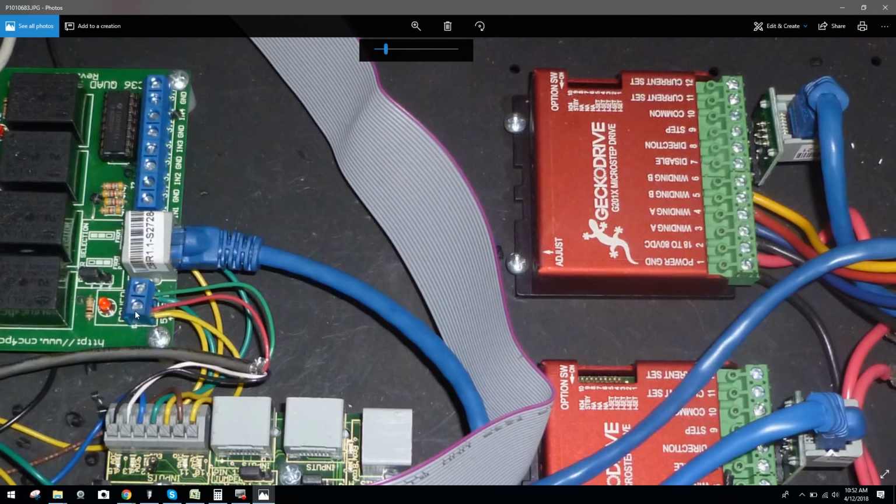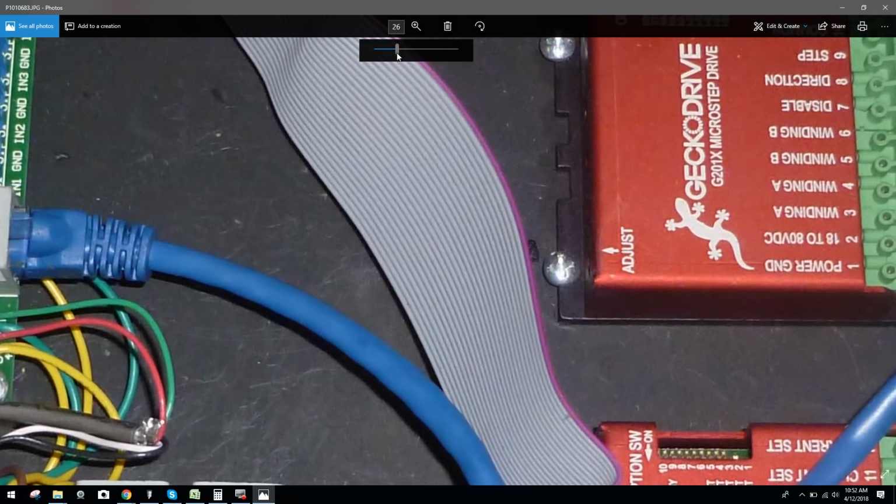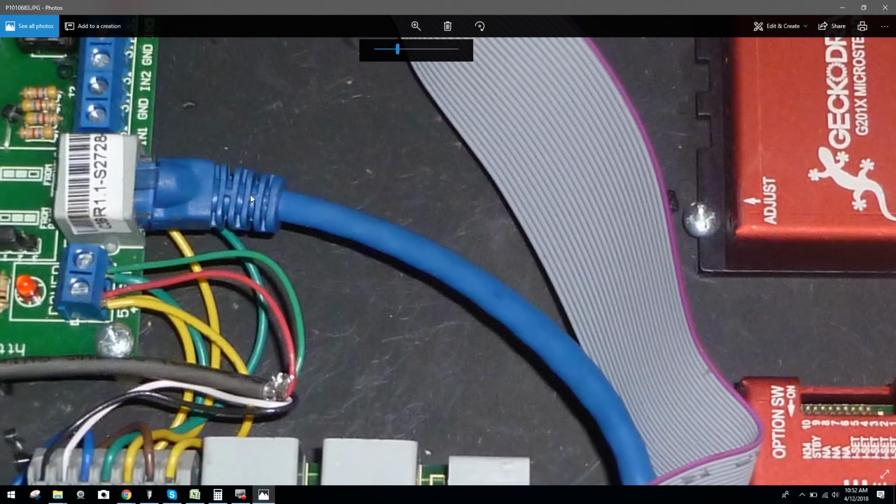If we look over here at these terminal blocks, you can see we actually have three conductors going into one terminal block, guys. Over here, you've got two conductors going into this terminal block, and what's really interesting is the more we zoom in and take a gander at this, you can see your conductors aren't even fully inserted inside the terminal block.